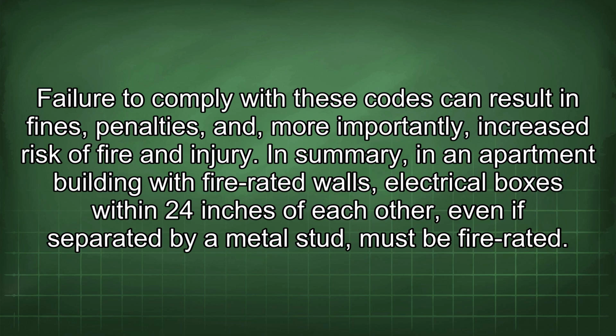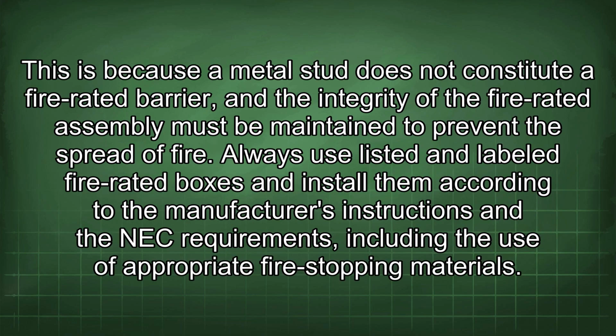In summary, in an apartment building with fire-rated walls, electrical boxes within 24 inches of each other, even if separated by a metal stud, must be fire-rated. This is because a metal stud does not constitute a fire-rated barrier, and the integrity of the fire-rated assembly must be maintained to prevent the spread of fire. Always use listed and labeled fire-rated boxes and install them according to the manufacturer's instructions and the NEC requirements, including the use of appropriate fire-stopping materials.